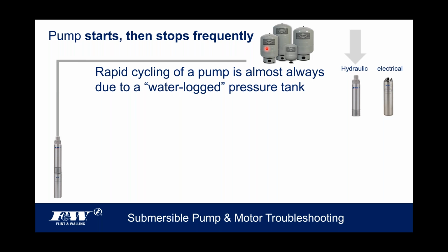But even here, if we've got rubber diaphragms or air cells or bags in these tanks, which act as a barrier between the air charge and the water so that water can't absorb that air anymore, if one of those diaphragms or air cells or bags ruptures, over time you're going to lose air out of that, and you're going to end up with a waterlogged tank. So again, when you hear of a pump coming on and off, on and off, on and off frequently, more than likely that's due to a waterlogged tank.